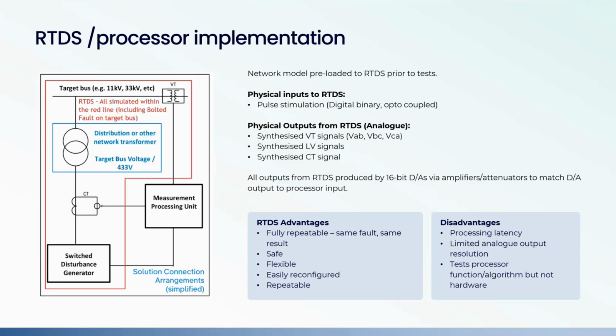So, whereas previous model validations compared RTFLM results, which are derived entirely from hardware measurement, with models derived entirely from lists of parameters, and hopefully accurate lists, in this situation, the RTDS situation, any errors or omissions in the input data, for instance, incorrect cable length, would affect not only the calculated fault level, but also the network response to stimulation. So that means we can compare like with like. The RTFLM result will be affected just as the modeled fault level is, so the comparison is now much less dependent on the quality of the input data.